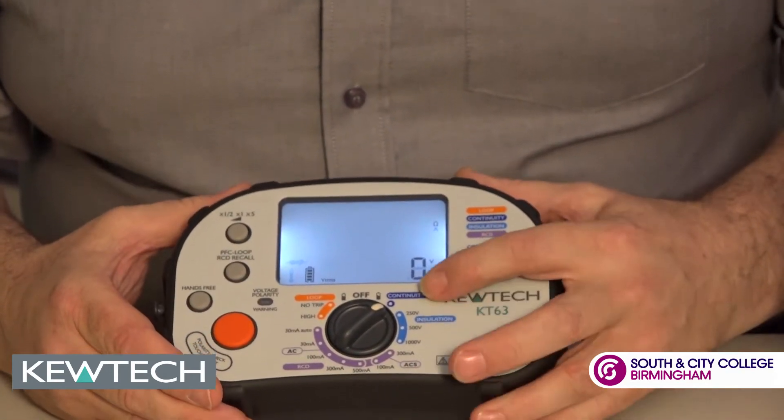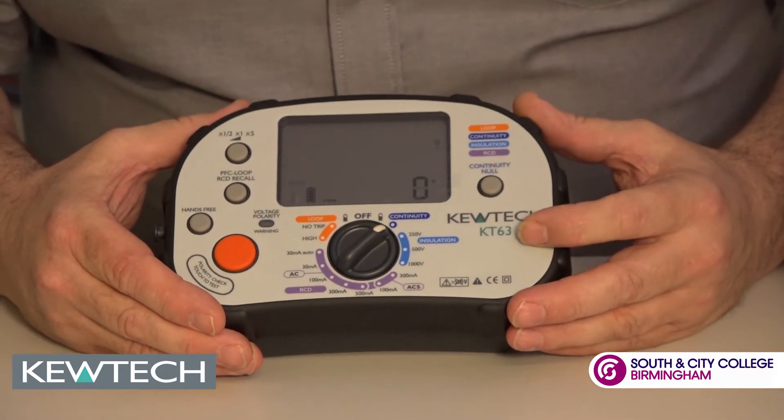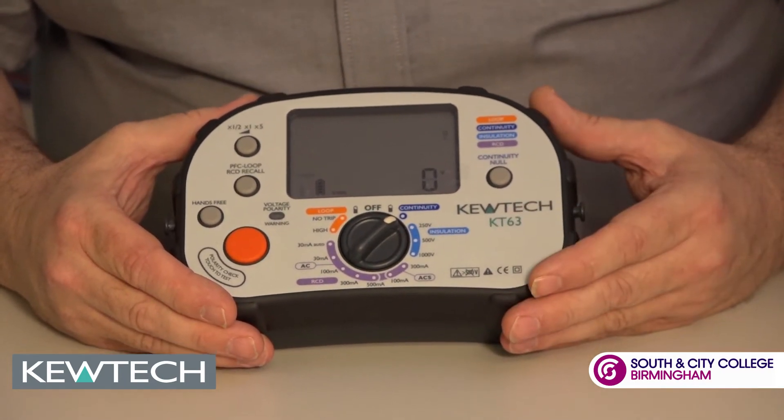First thing we put it on is continuity testing. Auto ranging, 200 milliamps, live circuit protected — so you don't have to worry about putting it on a live circuit, you'll get a warning. You can also use this with your PAT adapter for doing your dead PAT testing.